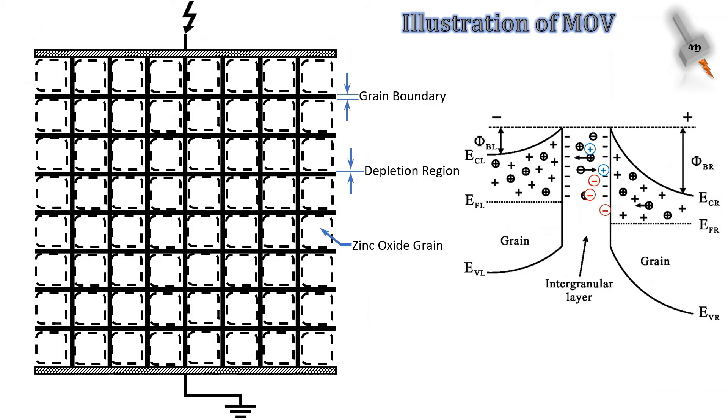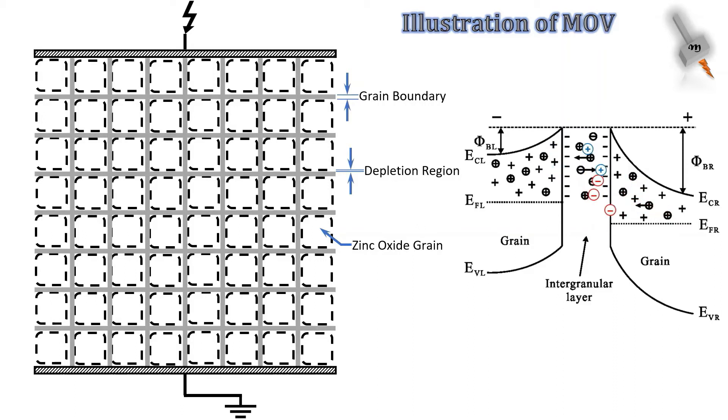When voltage is applied to a Surge Arrester, it ultimately gets applied on the MOV. Due to this applied voltage on MOV, the grain boundary experiences charge accumulation and slowly the charge starts crossing the grain boundary. As the applied voltage further increases, more and more charge starts crossing the grain boundary and hence there is an increase in current flowing through the MOV.